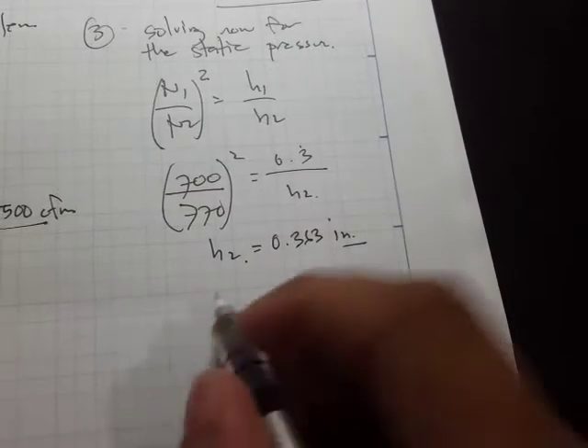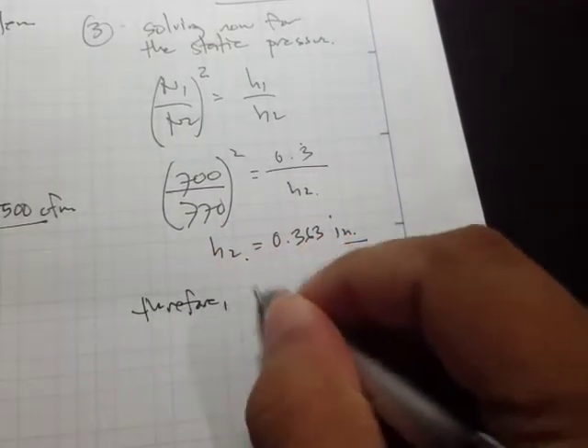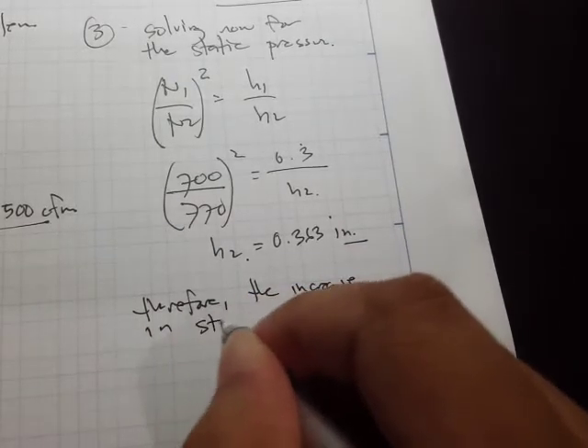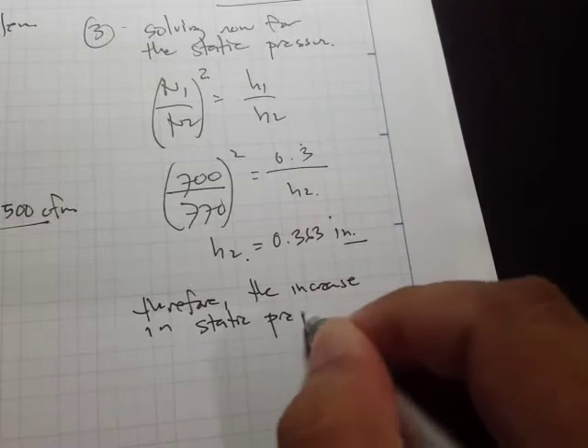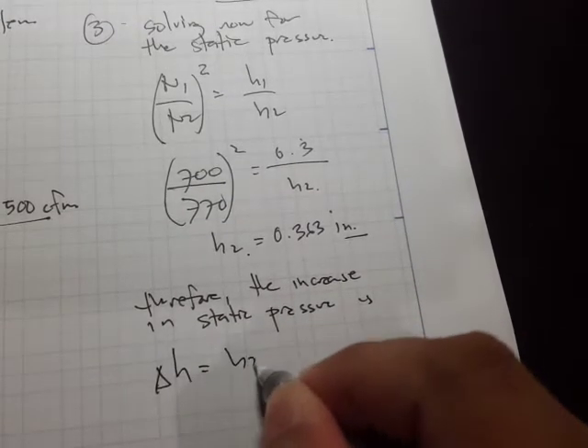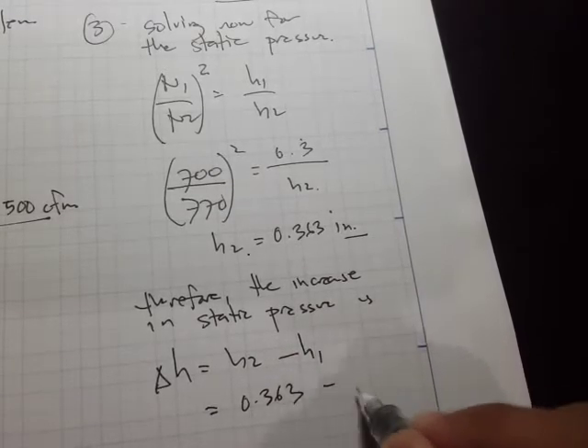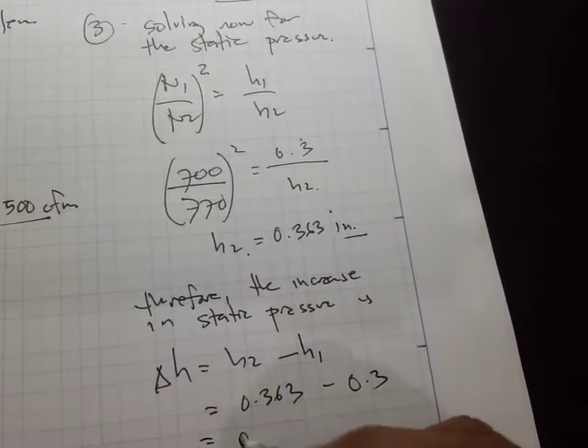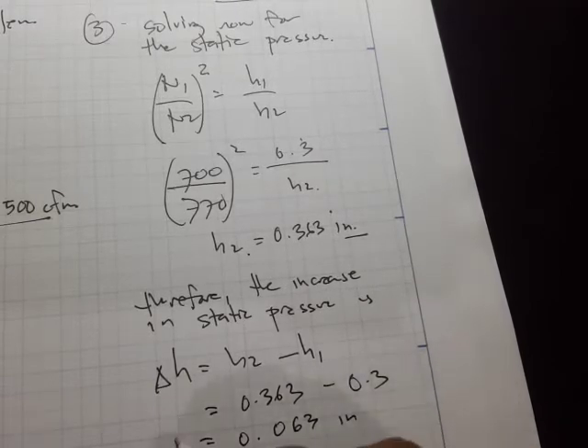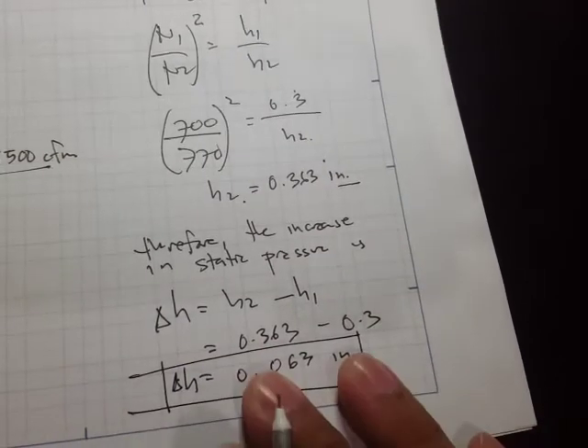Calculating: h₂ = 0.3 divided by (700/770)² = 0.363 inches. We are asked to find the increase in static pressure, which is the difference between final and initial. Therefore Δh = h₂ − h₁ = 0.363 − 0.3 = 0.063 inches.